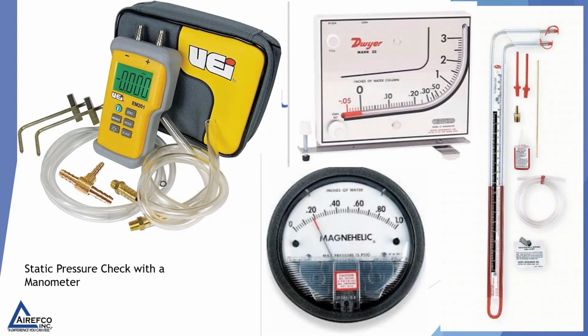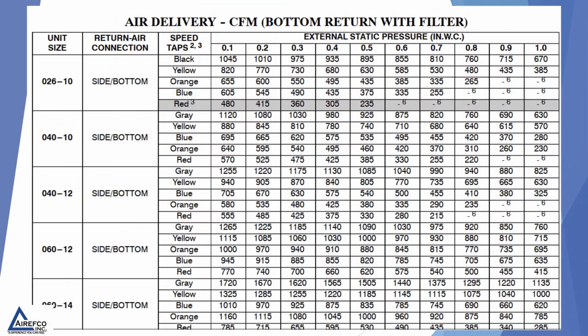Another way to determine CFM through any air handler or furnace would be to use a static pressure check with a manometer. You could use either the older Magnehelic, a slope type gauge with a liquid in it, or the new digital manometers. Every manufacturer puts out air delivery tables for their air handlers. By reading the static pressure on a particular system, you can go down that column of the static pressure you're reading on your system and read what CFM is being delivered through the ductwork from that air handler.